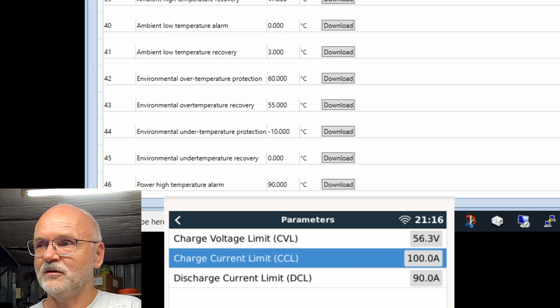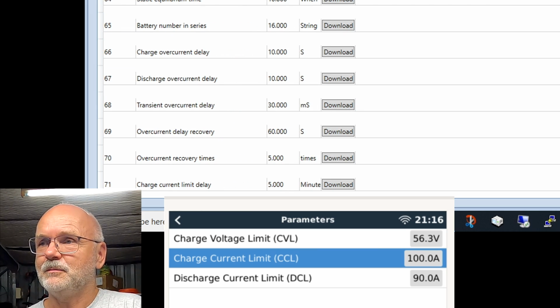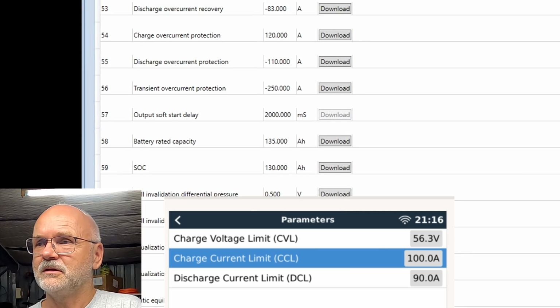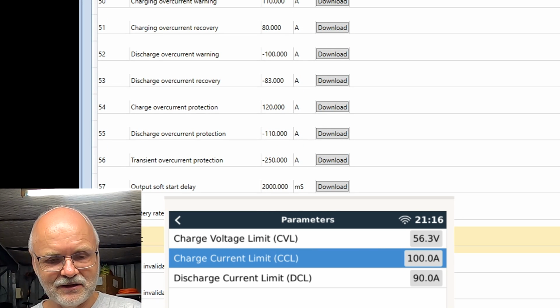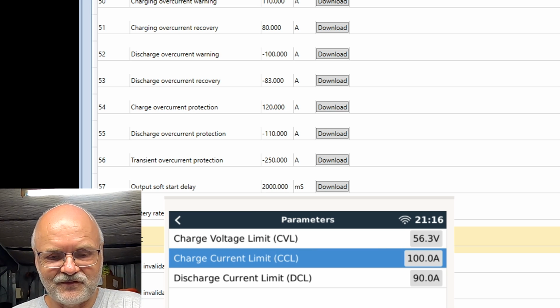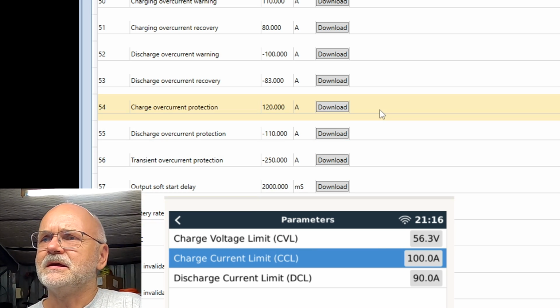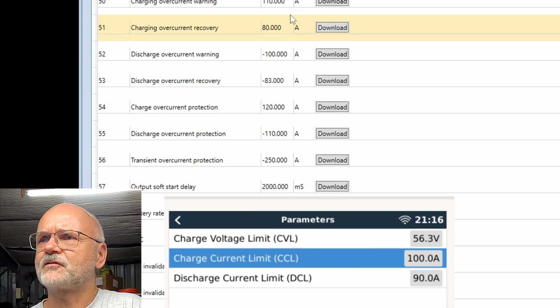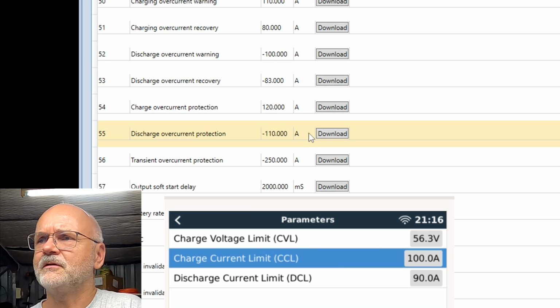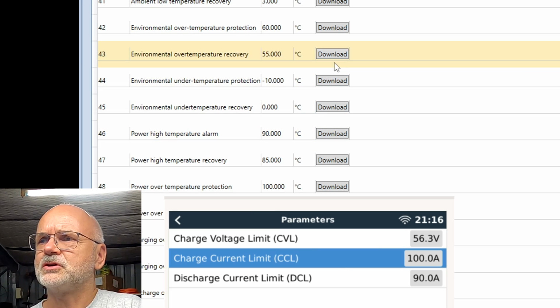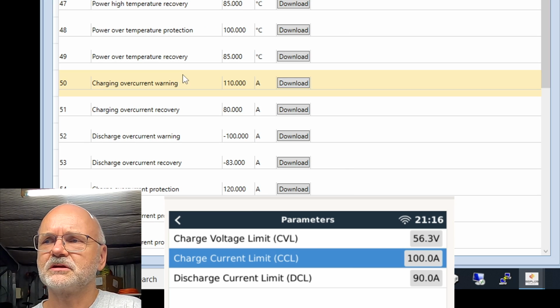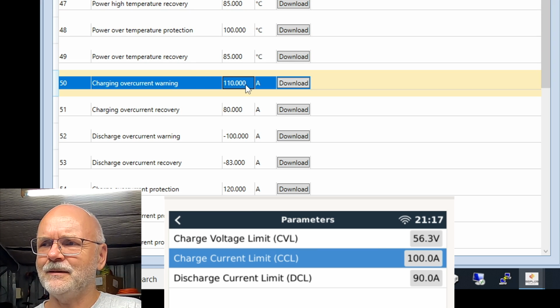Okay, let's move on from this disaster. A little bit further down, here are my amp settings. So we want to change the charge current limit, CCL. It sits on 100 amps at the moment. And charge current limit, where is it? Charge overcurrent warning, right, that's the one. It sits on 110, so it looks like we need to set it 10 amps higher.